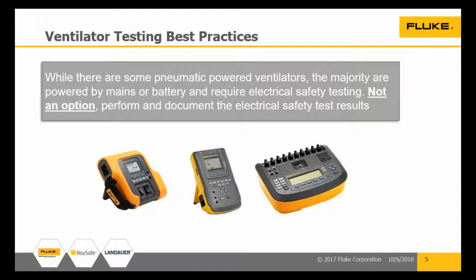I think it matters where in the hospital you're testing—it could be a wet location, so you'd pick the higher voltage. You're testing the insulation jackets around the conductors to make sure you don't have current induced in an adjacent conductor, and certainly no arc-over. So NFPA 99 would be all over that, no arc-over, because it's all about fire protection.